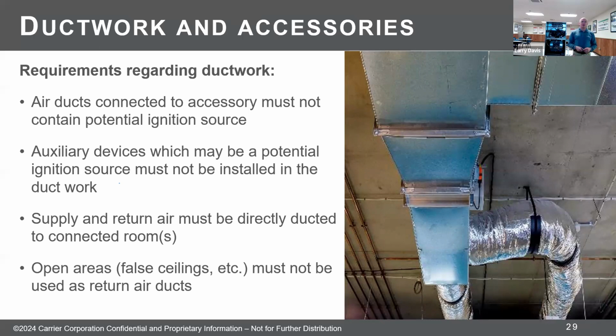Supply and return duct must be directly ducted to connected rooms. What they're saying here, and you see at the bottom bullet, using a false plenum or an open return above a lay-in ceiling, is that that's no longer going to be acceptable. We've asked for some clarification on why that is, and haven't really gotten a response. My guess is that the majority of the time, in a light commercial application, you have an open plenum above a ceiling and you have the supply duct running through that plenum. I think maybe the concern is if there is a leak in the supply duct, then we're just recirculating air and we're not getting the full dissipation. We're not being able to use the full square footage of the building to dissipate that refrigerant.